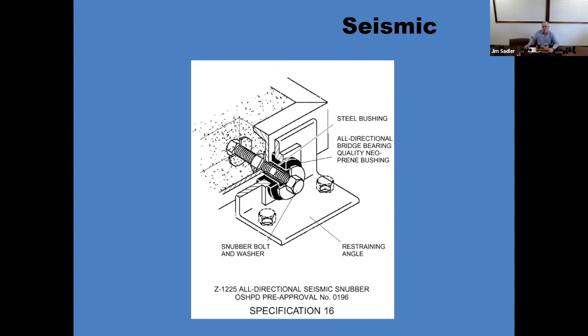Okay, so that covers the basics of vibration isolation and seismic. One important aspect with vibration, and really the best isolator we can provide, is an air spring. What can happen with high-speed equipment operating at 3,600 RPM, 60 Hertz, is that despite the theory, if you put the equipment on steel springs, that high frequency energy will travel down this coil like a water slide and get into the structure.